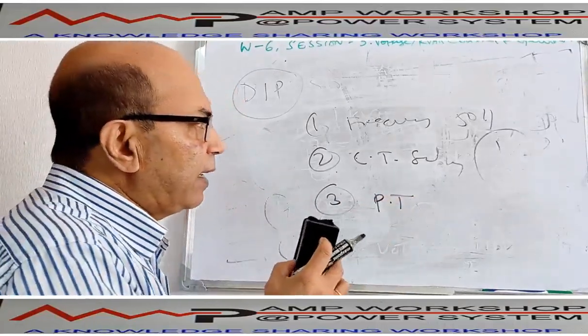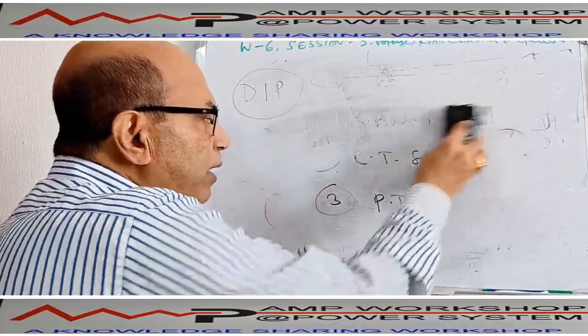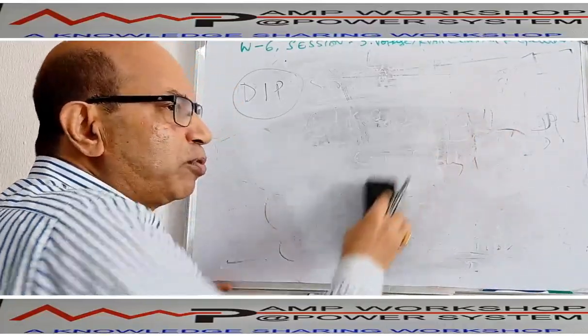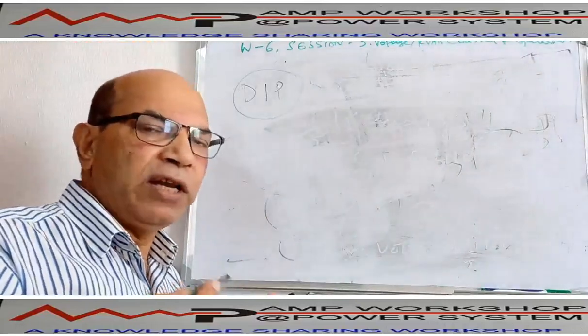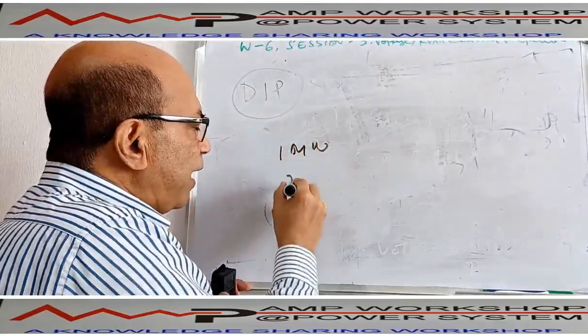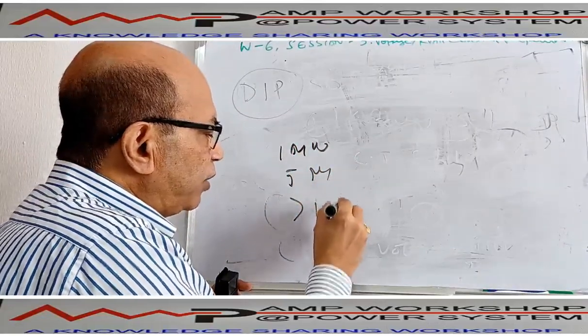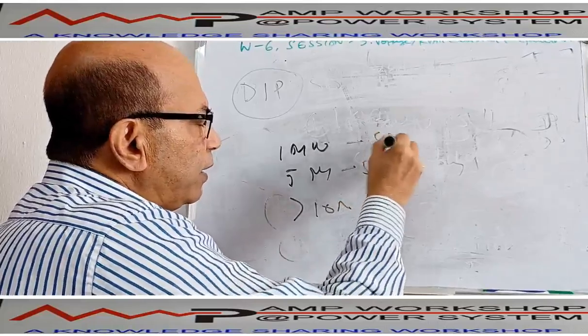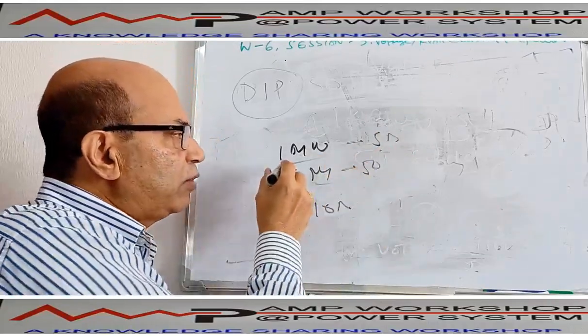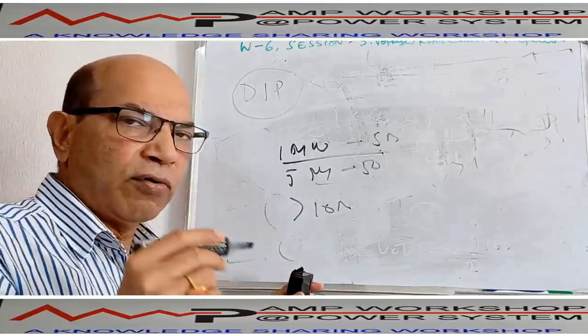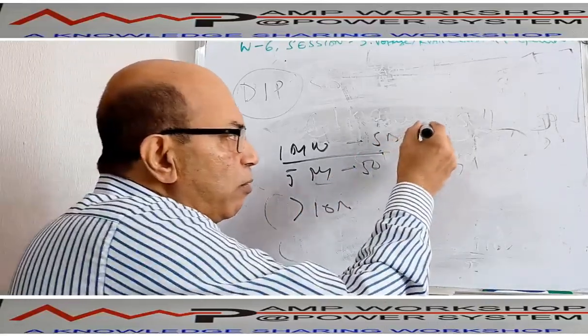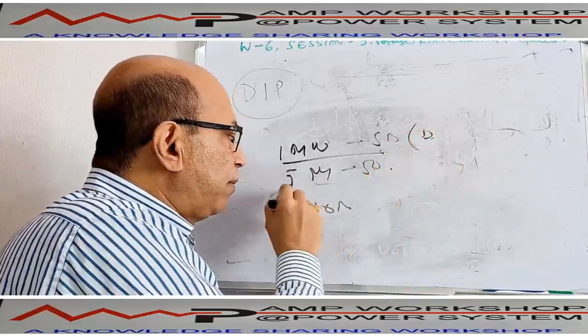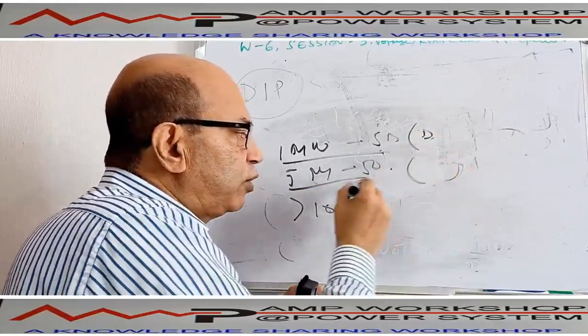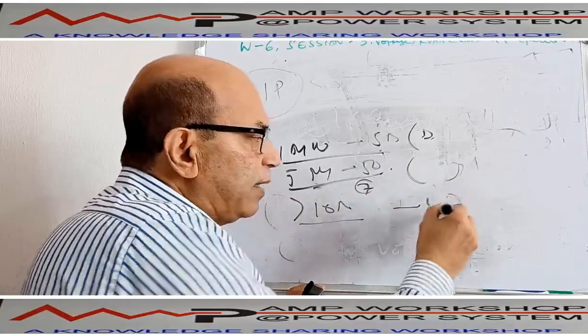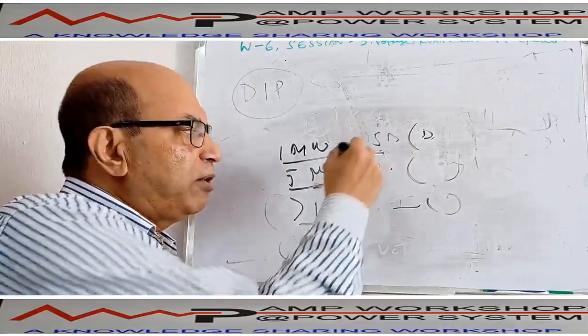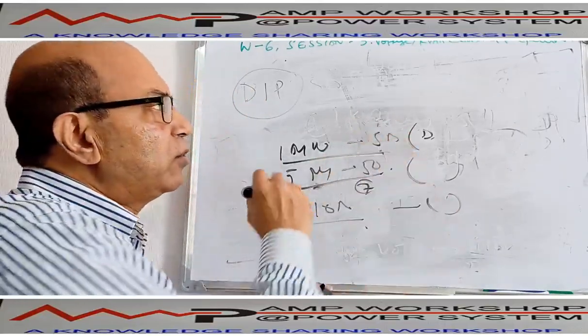Okay. Then there are multiple DIP switches for the machine rating. What is that? The same AVR can be used for different sizes of machine. Suppose you can use a 1 megawatt machine, then maybe a 5 megawatt machine, then maybe more than 10 megawatt machine. It may be 5 to 10 megawatt, it may be 1 to 5 megawatt. So these are the ranges. Now, if you want to use the AVR for this range, then the AVR operation will be different. So there will be one switch for this purpose. Suppose the machine rating is 7 megawatt, maybe there is another DIP switch to select this range. So this type of multiple DIP switch may be available to select the machine rating. So that is also available.